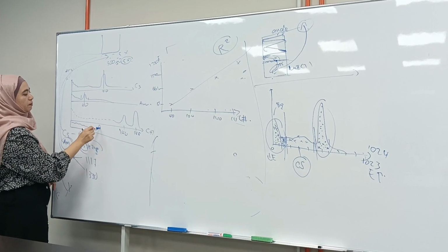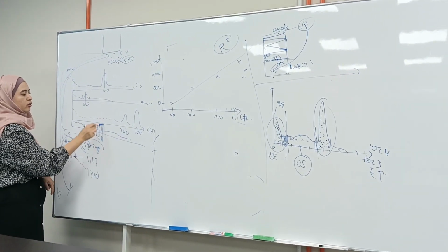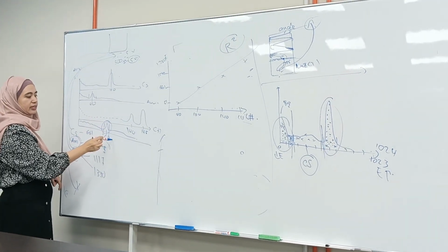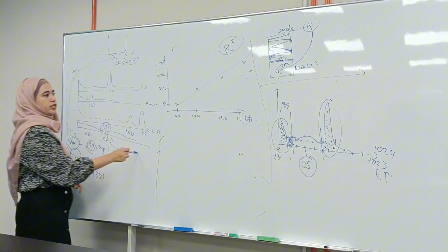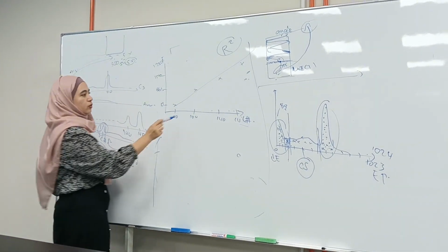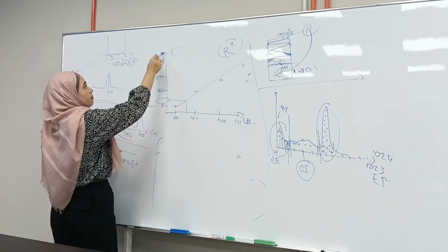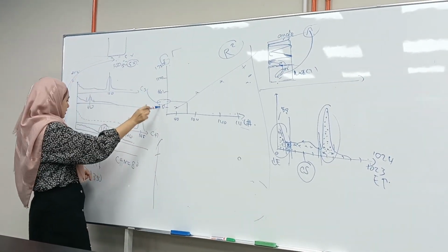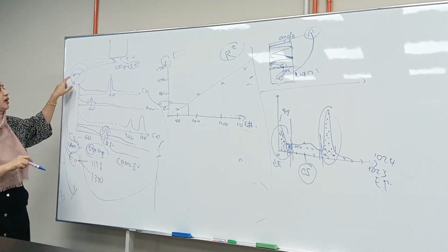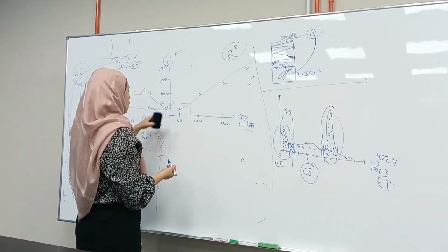And from this, what you will see, again, background, peak, but you know the channel number, but you don't know the energy because it's unknown. So you bring in the channel number, let's say M, to here, let's say channel M is equivalent to 80. You bring 80 here, you'll be able to find the energy, and from the energy you will identify what is the unknown source, Y.